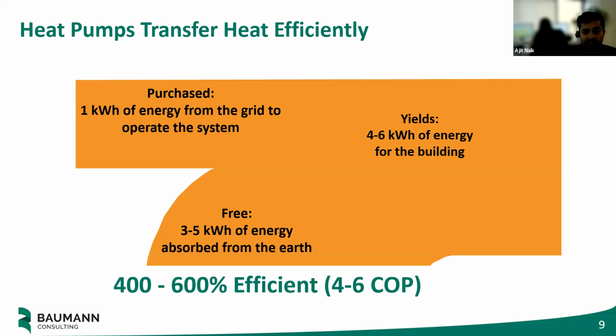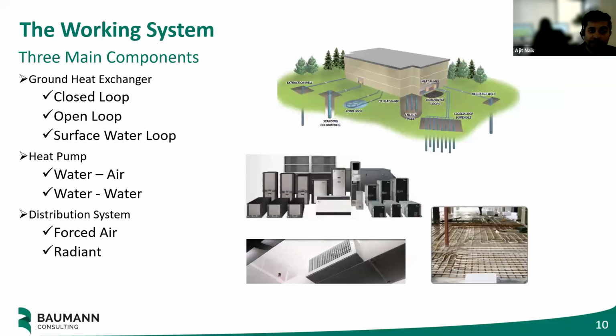So when we put in our 1 kilowatt hour of electricity from the grid to operate it, we end up getting more. Instead of just 2 or 3 kilowatt hours of energy absorbed from the air, we get 3 or 5 kilowatt hours absorbed from the earth. This ends up with 4 to 6 kilowatt hours of energy total as heat into the building, so these are like 400 to 600% efficient. Whereas air source heat pumps are really only 2 to 300% efficient, a coefficient of performance of 2 to 3, geothermal heat pumps are often twice as efficient just because they're working with that thermal battery in the ground.